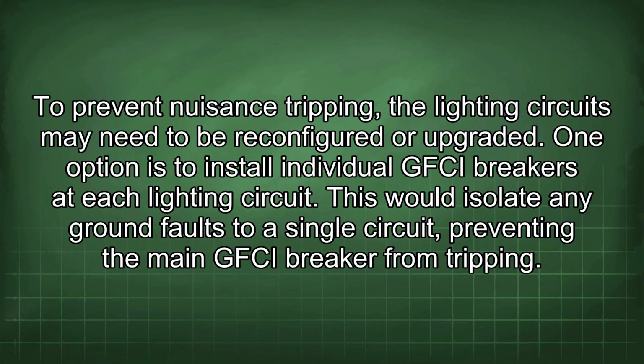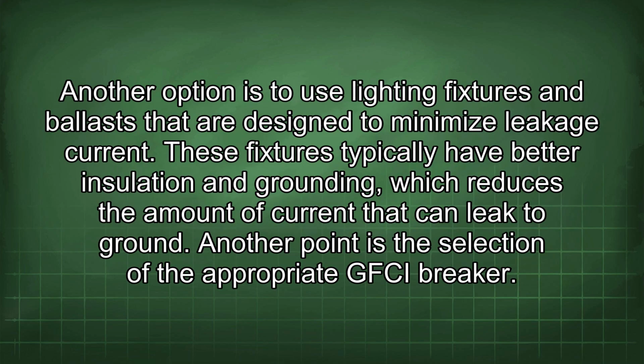To prevent nuisance tripping, the lighting circuits may need to be reconfigured or upgraded. One option is to install individual GFCI breakers at each lighting circuit. This would isolate any ground faults to a single circuit, preventing the main GFCI breaker from tripping. Another option is to use lighting fixtures and ballasts that are designed to minimize leakage current.